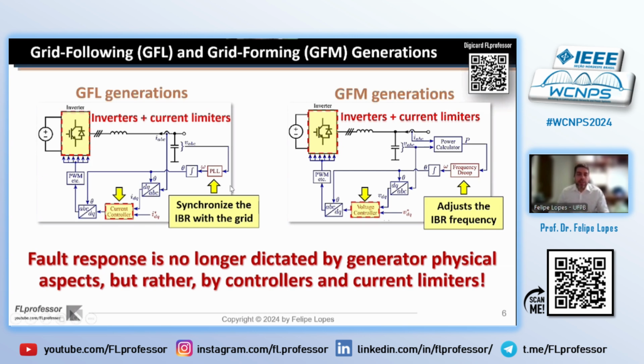But there are other challenges here. If we consider grid following technologies, for instance, these generations synchronize with a given grid by means of phase-locked loops, which estimate the magnitude and angle of voltage at the connection point in order to synchronize the generation with the grid. But when these voltages present very critical sags, these PLLs can present instabilities, and as a result, the estimated frequency can present errors, leading the IBR to operate with off-nominal frequencies, leading also the currents that are synthesized in their output to present a atypical behavior.